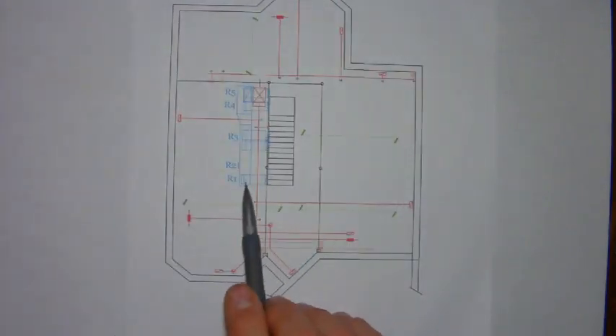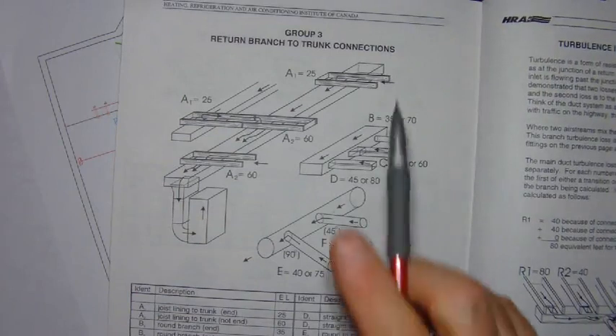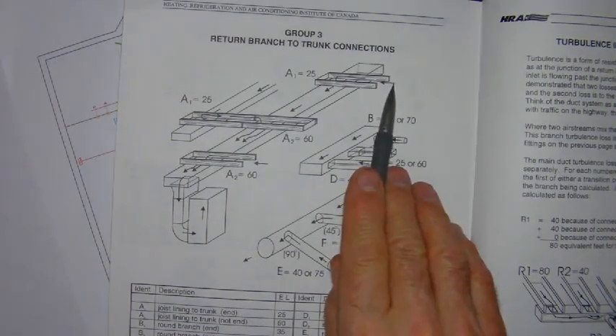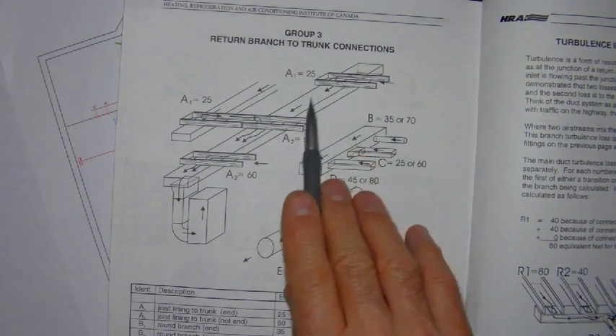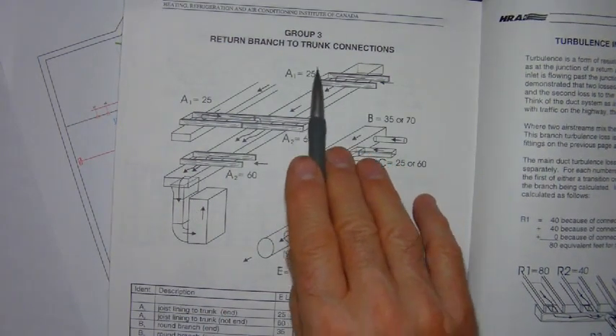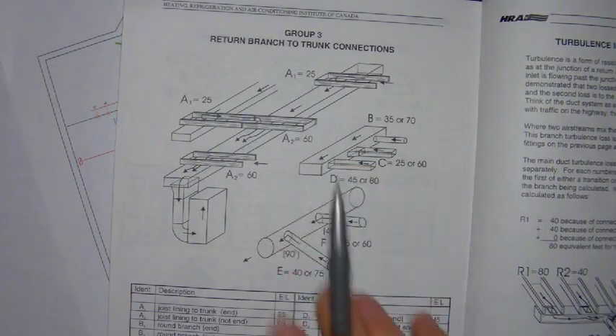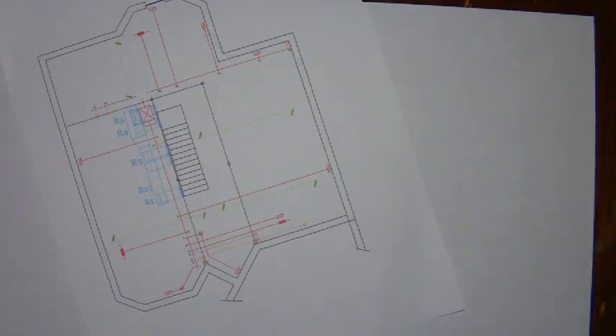Now the air needs to enter the duct at this location. And if you recall in group three, when the air from the furthest return air away from the furnace enters the duct, there is an associated equivalent length of 25 feet.